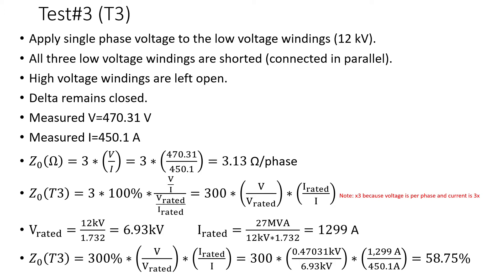Test 3: apply single-phase voltage to the low voltage winding — in this case the 12 kV winding, just as an illustration. All three low voltage windings are shorted and connected in parallel. The high voltage windings are left open.